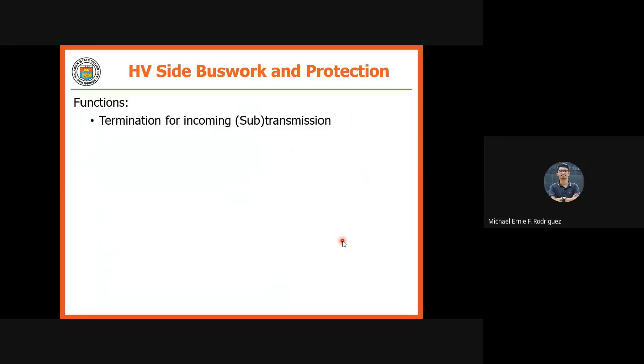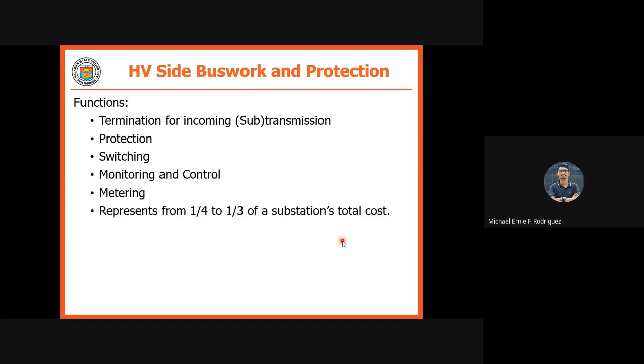So, apat yan. So, first, HV side, buswork and protection. Ano mga functions nito? So, this is termination for the incoming transmission. Protection. We have switching, monitoring and control, and metering. Take note, this represents from 1/4 to 1/3 of the substation's total cost. So ganun siya kamahal. So halos 1/4 up to 1/3.